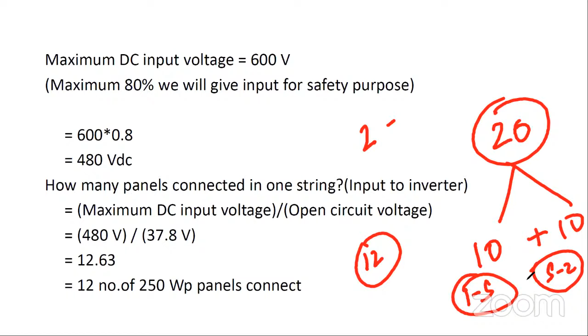So we are checking the parameters, whether the voltage is exceeding, whether the current is exceeding. As we know, 600 volt is the maximum voltage, but if you connect 10 panels in series, then the VOC will not be more than 380 volt. But the maximum voltage for the inverter is 600 volt. So 380 is less than 600 volt. Yes, we are safe.